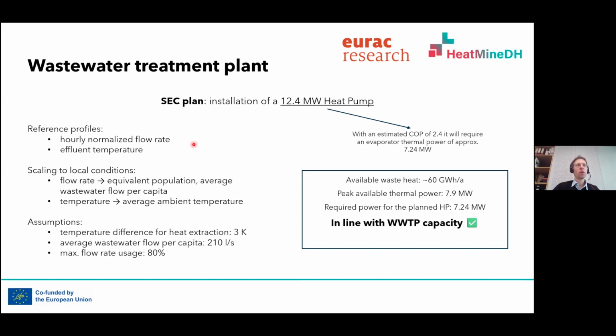In this way, we were able to consider both the temperature of the system, especially targeting the effluent of the wastewater treatment plant, and the flow rate. The flow rate can generally be estimated for a wastewater treatment plant based on the population size for which the plant is designed. We then made some assumptions about the temperature difference for heat extraction, and assumed to exploit about 80% of the maximum flow rate usage, and in this way we could reach these estimates about the power.